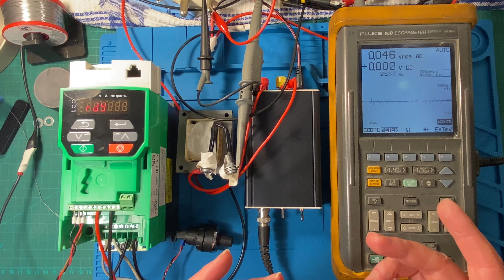That's going out to the motor. As you turn the frequency down, you see that voltage coming down. That's how AC drives work. You're controlling voltage and frequency, because the motor voltage is dependent on speed, which is a function of the frequency being sent to it, and so on. They're all related. So that's what's going on here.